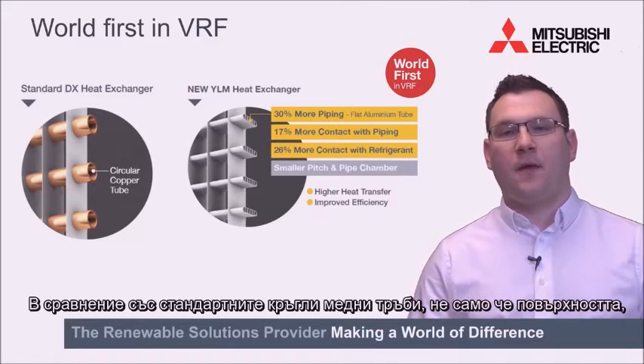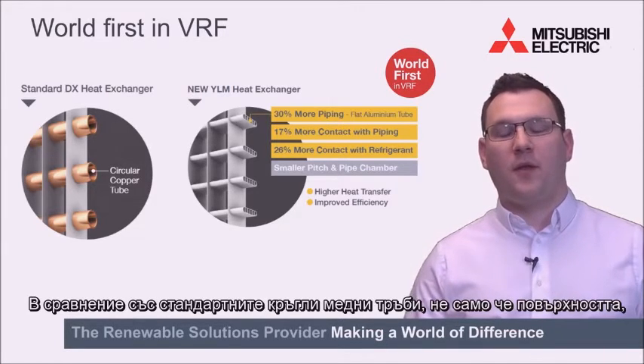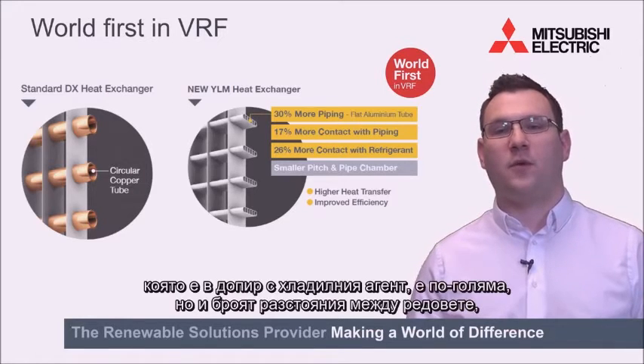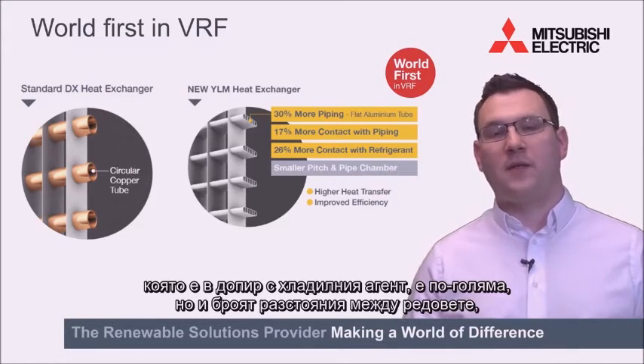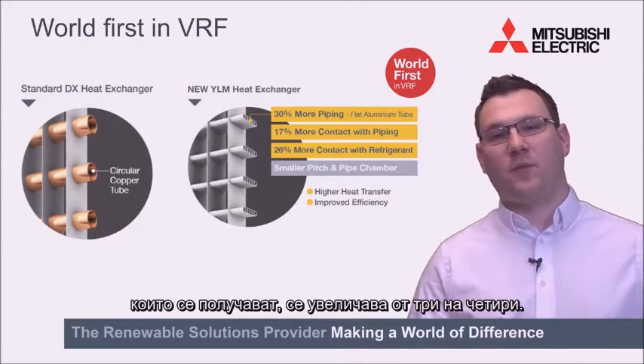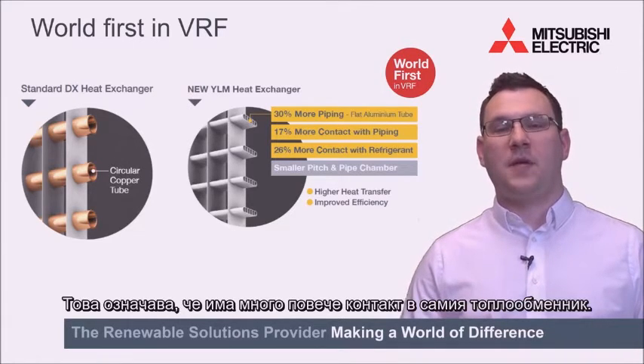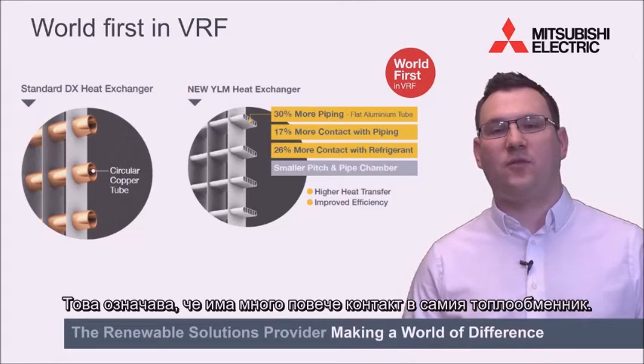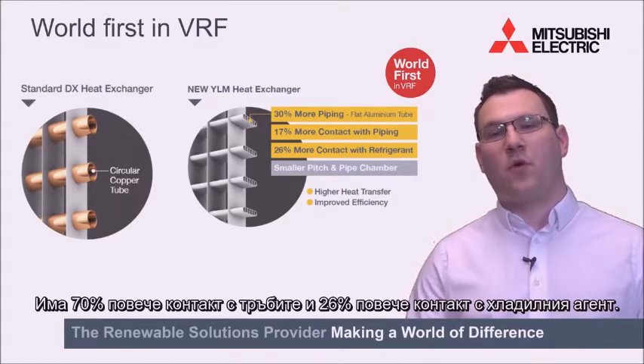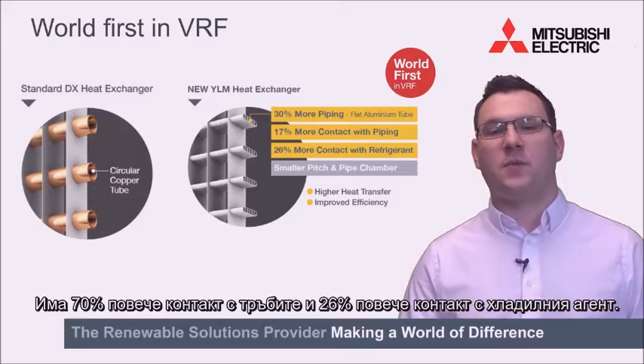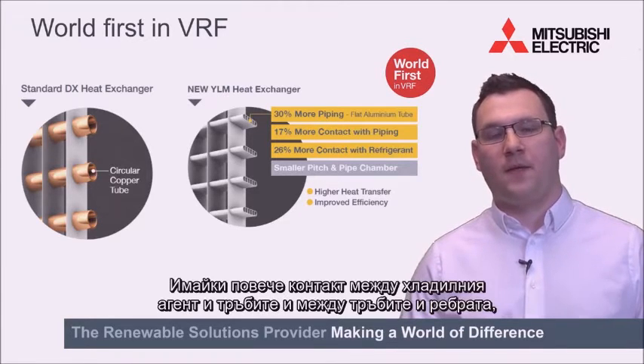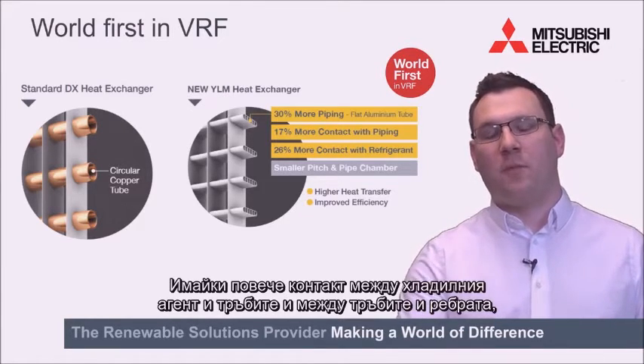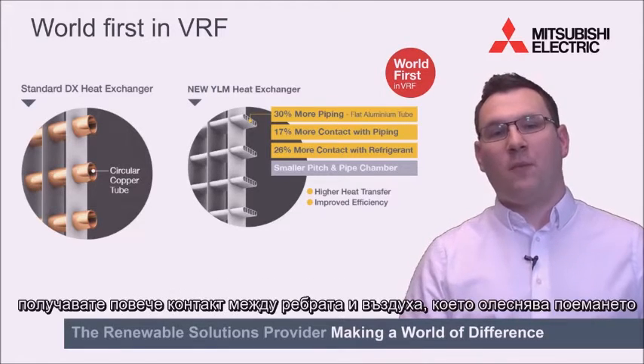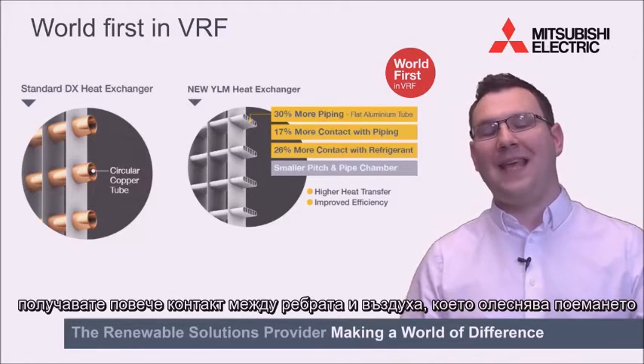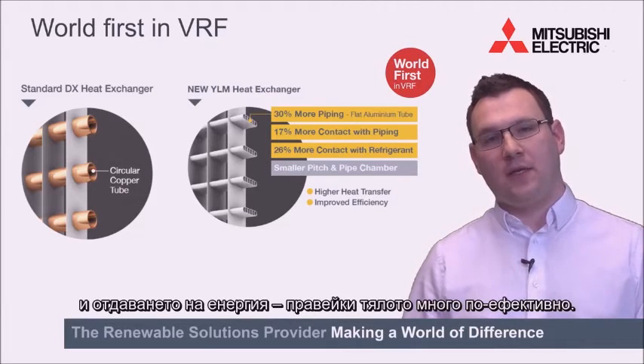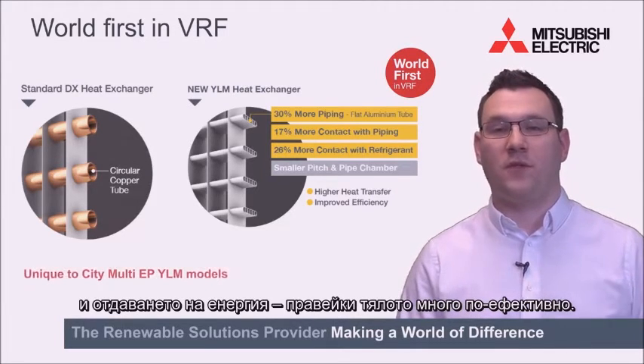exchanger. Compared to a traditional round copper piping, not only is the surface area available for contact with the refrigerant increased, but the amount of passes which you can get in an area is increased from 3 to 4. This means there's much more contact within the heat exchanger itself. You get 17% more contact with the piping and 26% more contact with the refrigerant. So by having more contact between the refrigerant and the pipe and the fins, you get more contact with the fins and the air, making it easier to absorb energy and reject energy, therefore making it much more efficient.